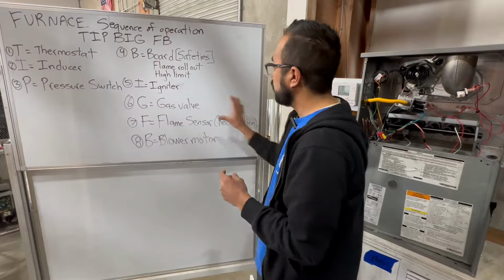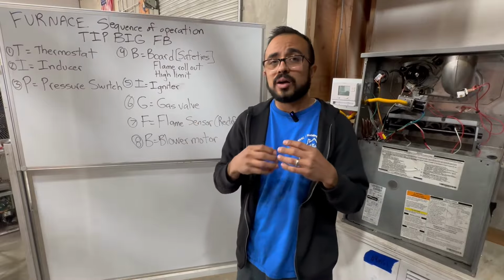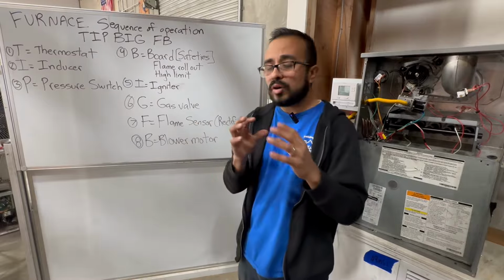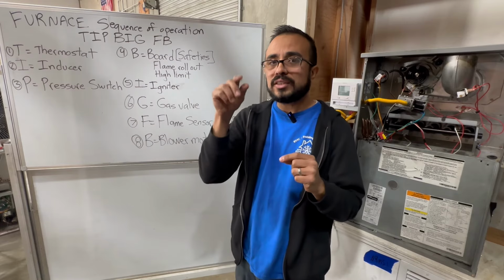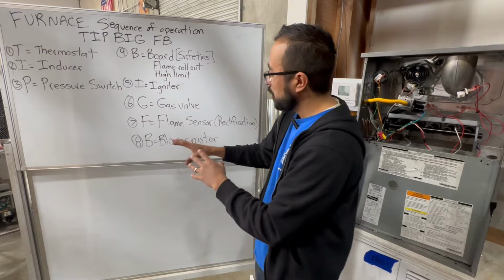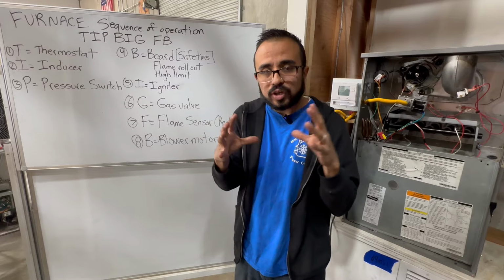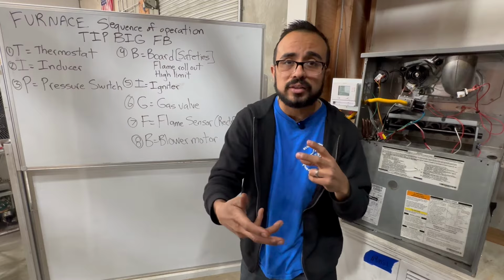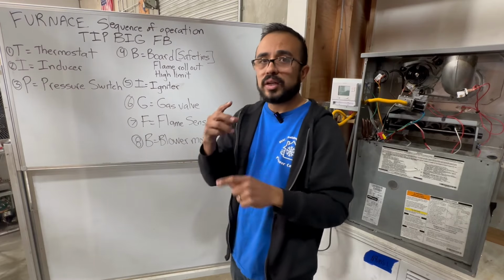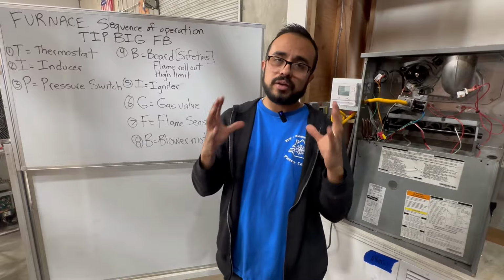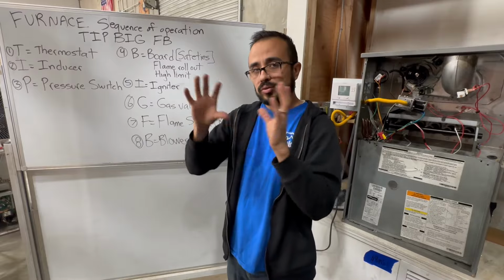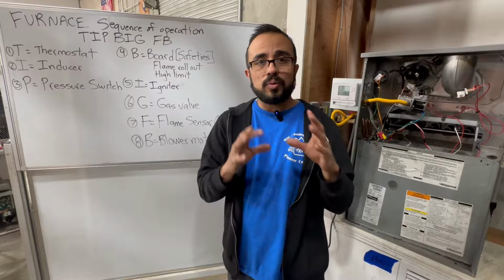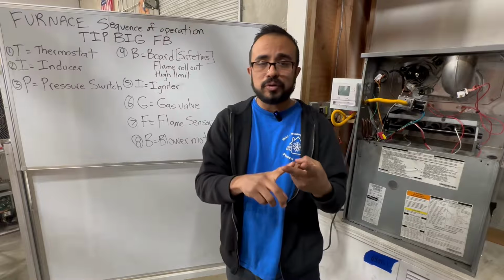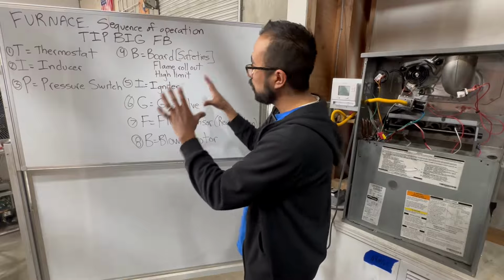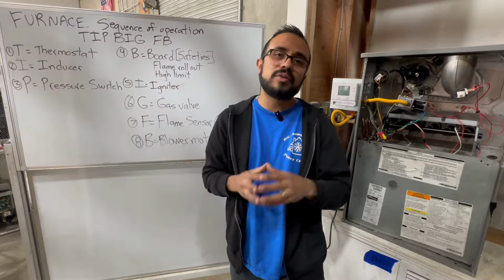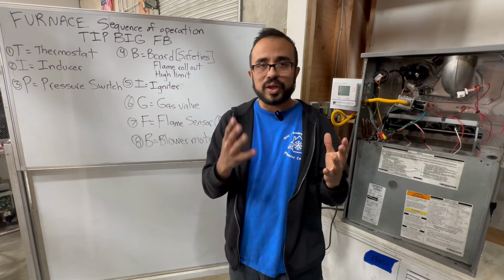So this is the flame rectification, and you're looking for 3 to 6 microamps, more or less. And your meter does have to have that symbol, the µADC, to be able to read that. And then the chamber, the heat exchanger area gets a little bit warm, gets a little bit hot, and after a couple of seconds, it sends power to the blower motor, and then it turns on. So yes, there's a lot of steps to a furnace working, 8 steps. But whether you're working on an 80%er, 90% or 96%er, you can take these principles to help you out in your next service call. I hope this video helps, and I will catch you on the next one.